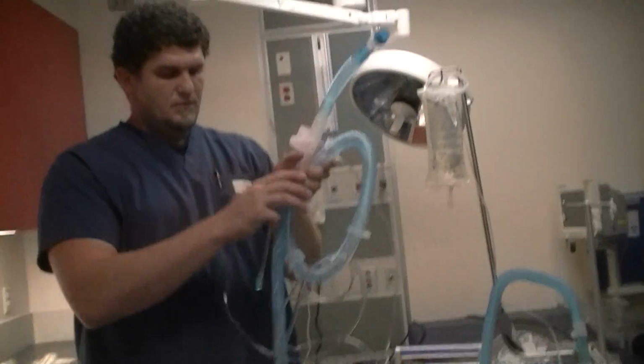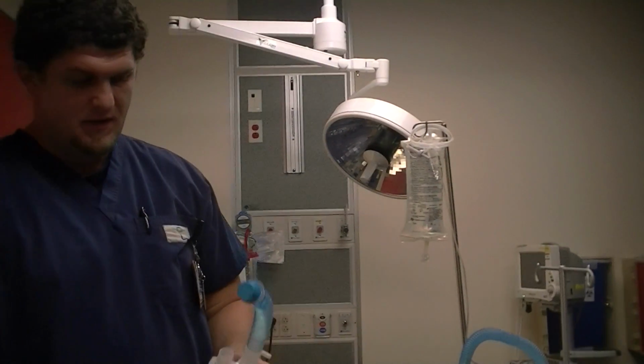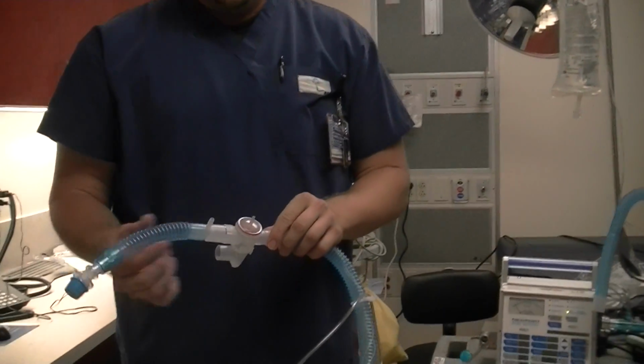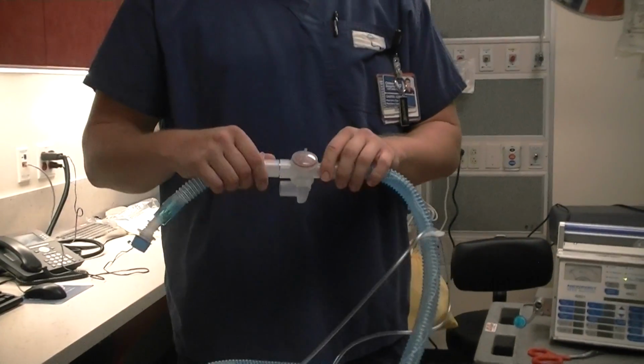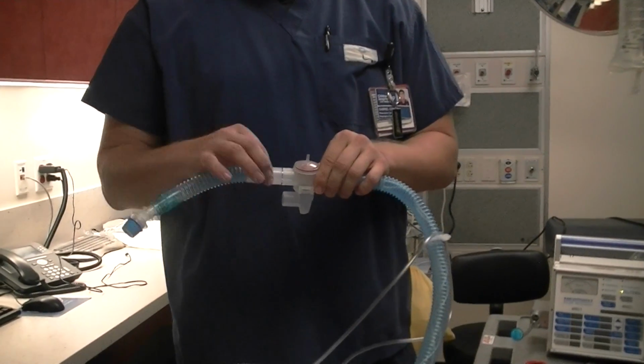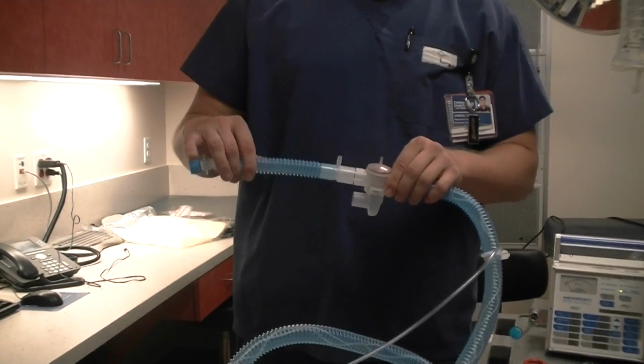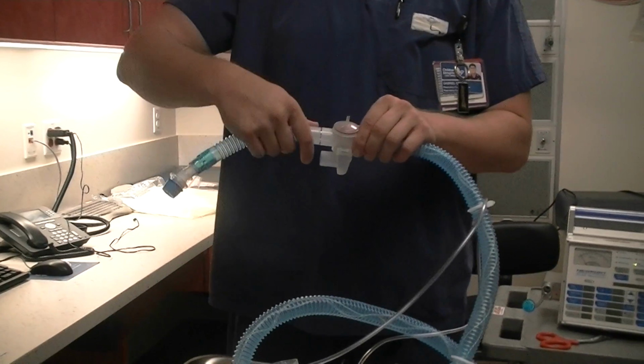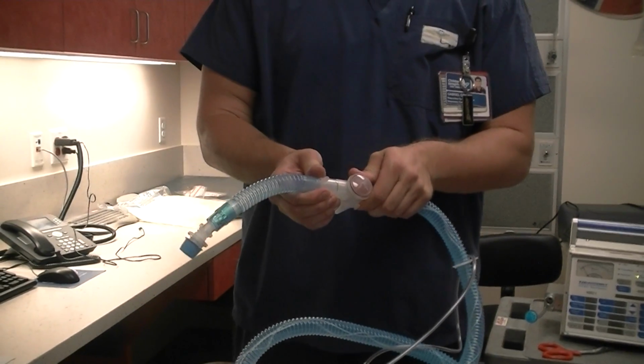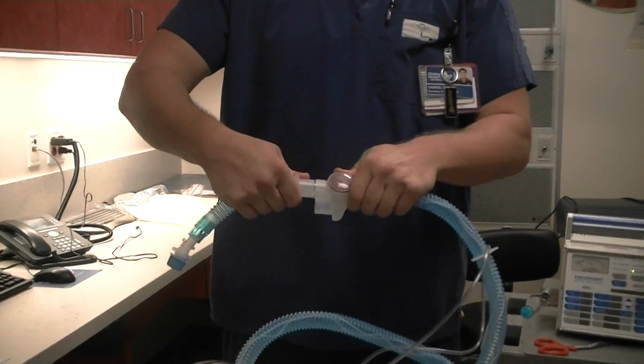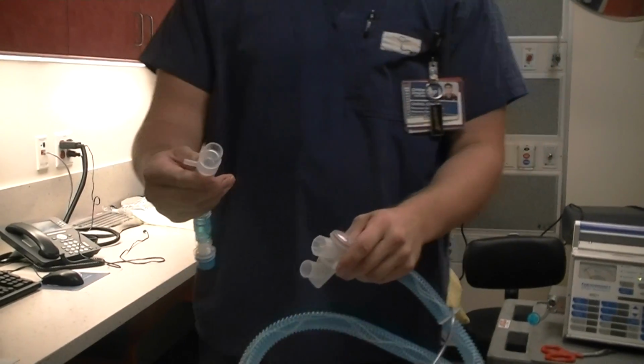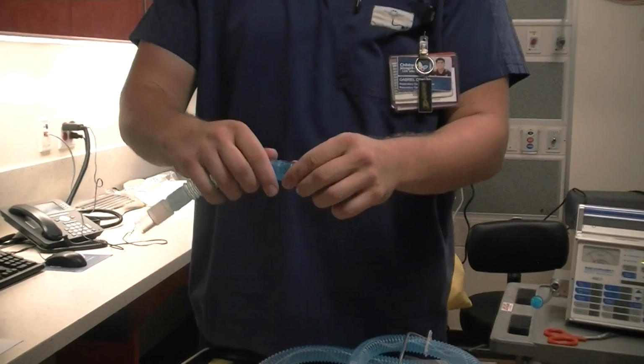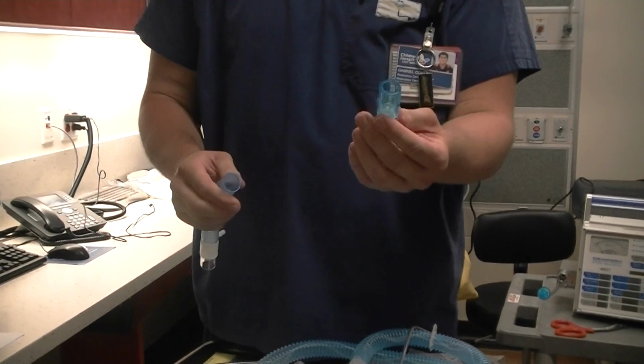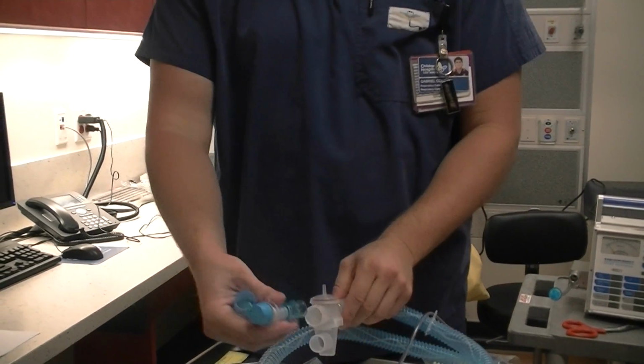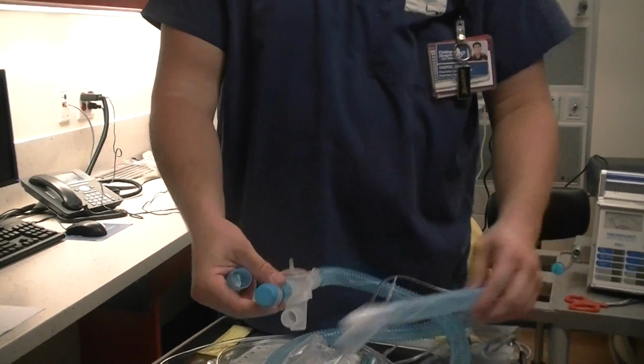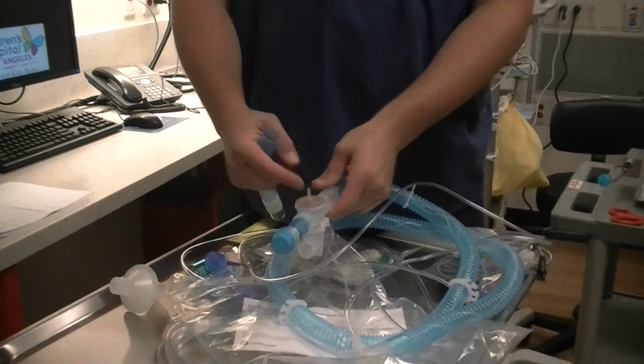Now, when you pull off this circuit, you'll notice the corrugated tubing after this exhalation valve. This has to come off. If this stays on, it is going to retain a lot of CO2, so you have to make sure it comes off, and you could actually utilize this piece. What you're going to do is pull this part off here. You're going to grab where the blue 15mm adapter is, and you're going to stick it right back on the front of your exhalation valve.